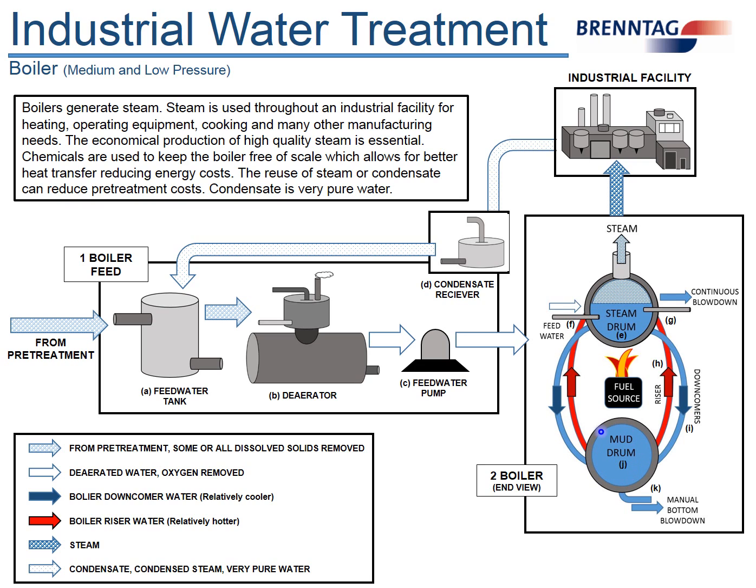The mud drum is designed to periodically remove any heavy material that may settle out. Typically, daily an operator will open the bottom valve and allow this material to come out. There's what's known as a continuous blowdown, and this is typically at the surface, right at the separation point between steam and water. What this does is continuously remove any contaminants that are concentrated in the boiler water.